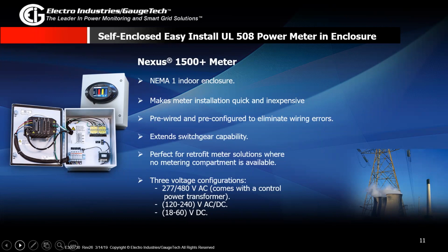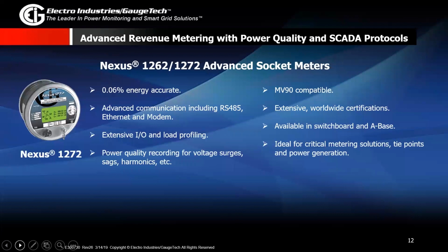So we talked about the newer Nexus meters in the Nexus line. We do have some older Nexus meters that a lot of you may be familiar with. This is the Nexus 1262 or 72 meters, which are the socket version. They also are 0.06% energy accurate and give you a lot of the basic applications that the other Nexus meters do. So they have the basic communication over RS-485 or Ethernet. It can also give you some power quality information on your voltage surge, sags, and harmonics. This is MV90 compatible since this is mostly for a billing application in the socket form.